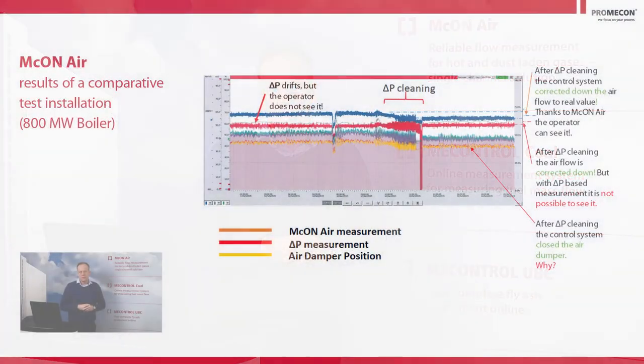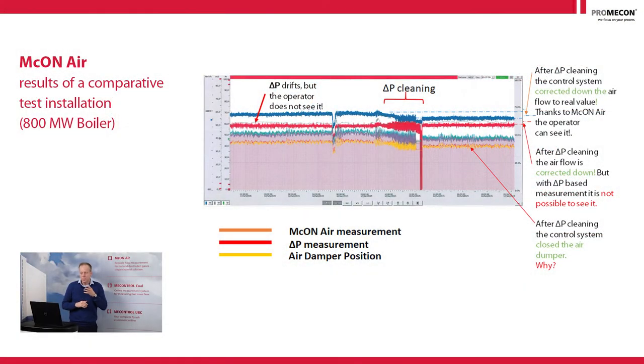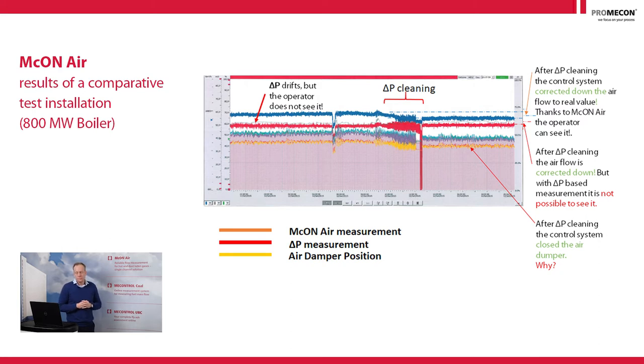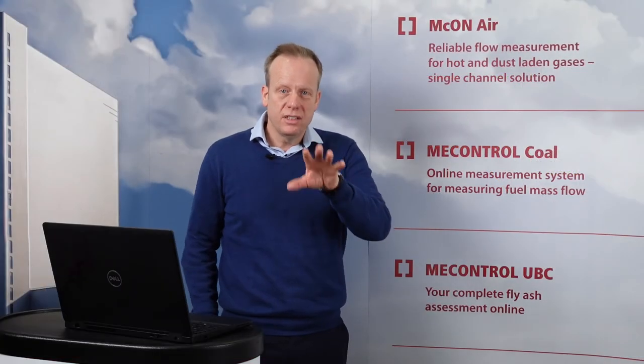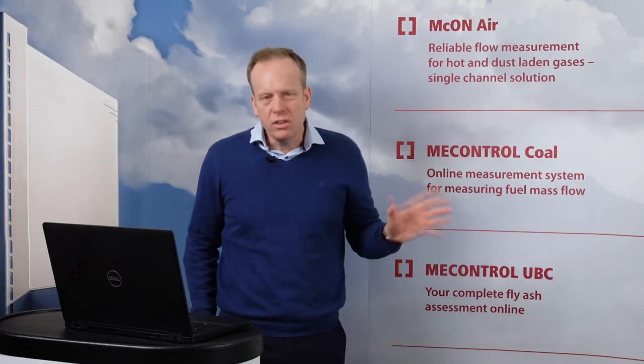Have a look at the next trend. This is a brand new 800 MW boiler — one of the most modern boilers in Europe. Same problem. The red line is the delta P, the blue line on top is the damper. You can see that before and after cleaning the damper has a different position, but the measurement value is the same. This is the problem of what we call analog measurement, and these measurements exist in thousands of plants around the world.